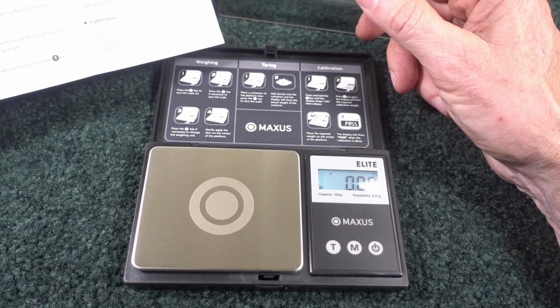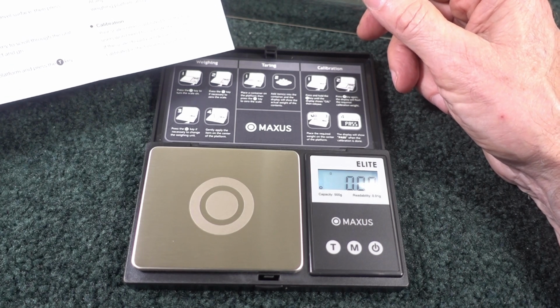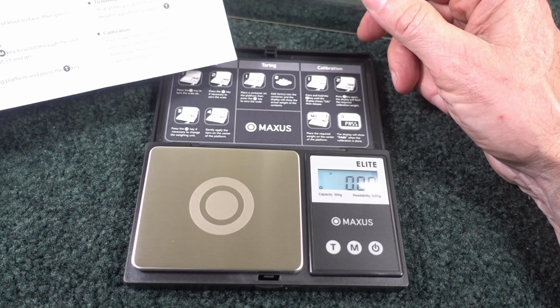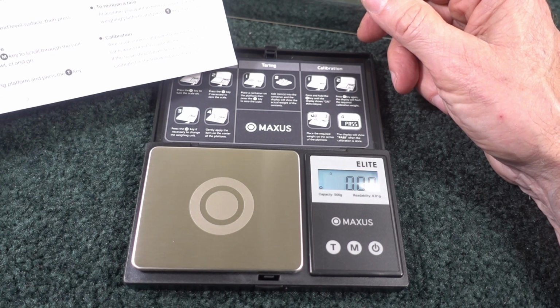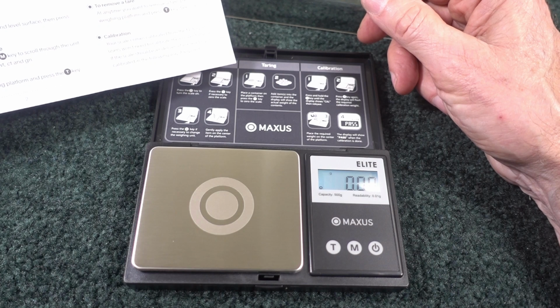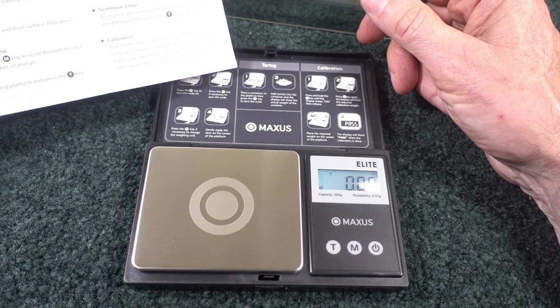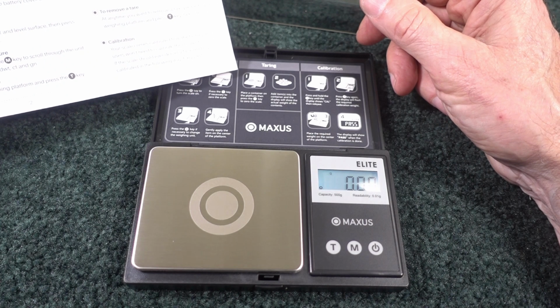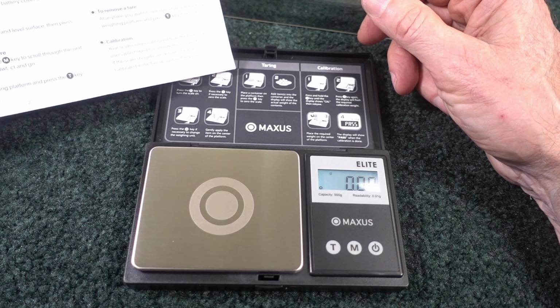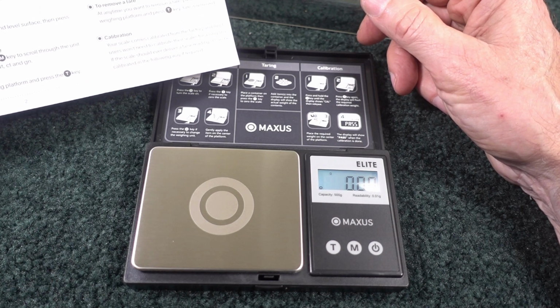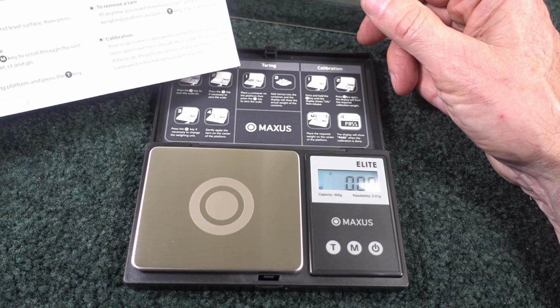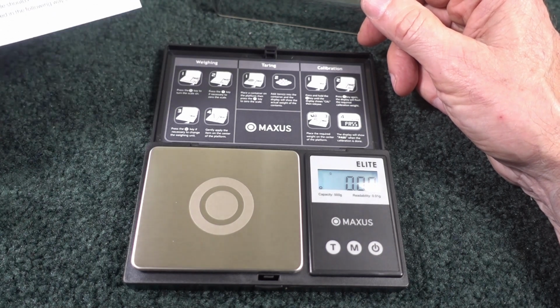Do not exceed the maximum capacity, which is 500 grams. Always weigh on a flat level surface, free from vibrations and drafts. Avoid exposure to extreme heat and cold. Avoid any kind of moisture. Avoid places close to strong radio waves emitting devices such as computers, cash registers, cordless phones, and cell phones. Gently apply all items to be weighed. Do not drop items on the platform. Avoid dropping or shaking your scales. Allow your scale to warm up for 30 to 60 seconds before performing calibration.